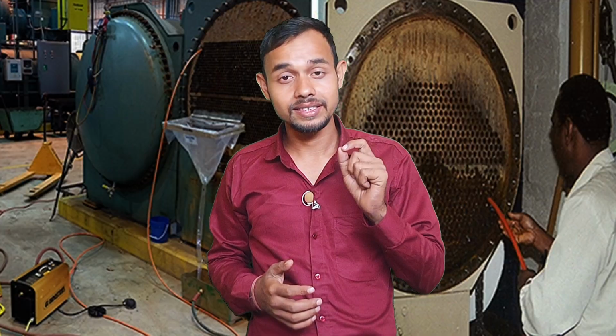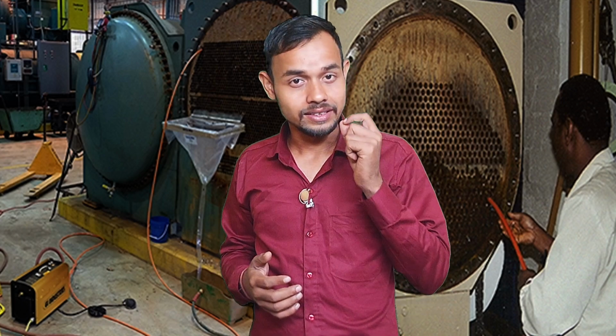Why must you do chiller descaling? So let's see what scaling causes. Scaling causes 30 to 35% efficiency loss, high compressor load, higher electricity bills, tube blockage and failure, continuous low cooling complaints, and lower equipment life. Okay, this is the biggest loss from chiller scaling. Okay, friends, the biggest loss is the huge rise in electricity cost. Chillers work harder, more energy is consumed. Friends, let's see why chiller descaling is important.